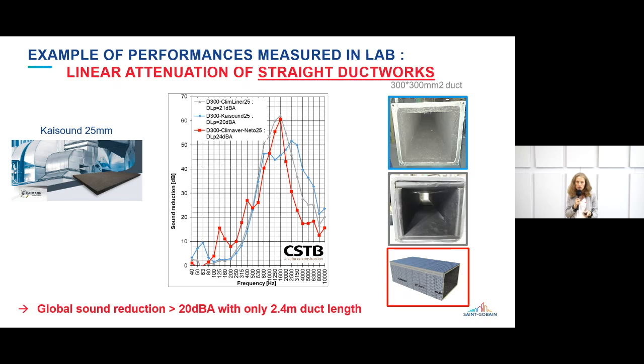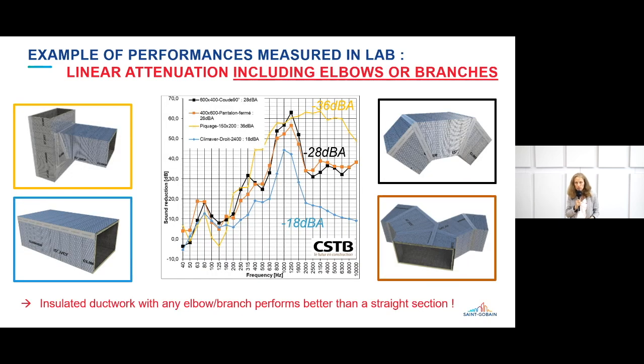If we now go to some shaped ducts, as you can guess, if you do have some shapes, then it's going to be even better. And in fact, that's what happens. You have here the blue line, which is a reduction of 18 dBA. It's only the 2.4 meters of a straight duct. And if on this straight duct you add a 90-degree elbow, then you have the black line, and you gain 10 dBA more. So with just one elbow of 30 per 30 centimeters internal section, you can have a gain of 10 dBA in just one elbow.